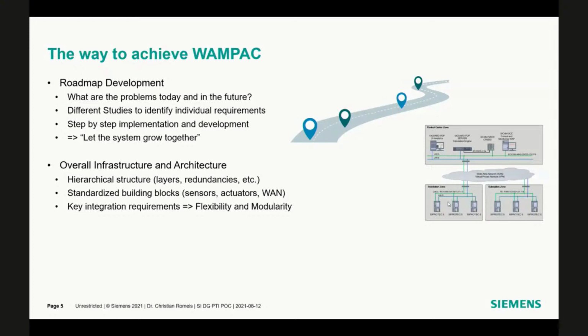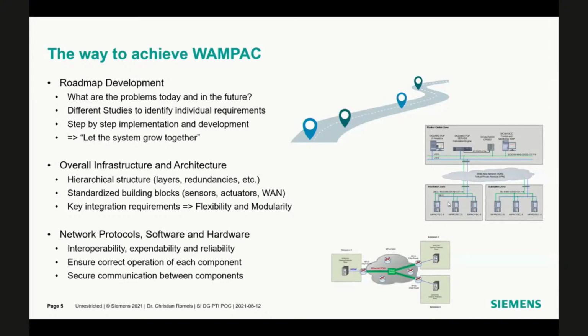And also you have to define standardized building blocks for you. Okay, which sensors I want to use, which actuators I want to use, what should I use in the wide area network, and you need to define key integration requirements. So it just must be flexible and expandable. And also you think about modularity, especially in the case of devices, because you can say, okay, I want my PMU standalone, or I can say I want my PMU in a protection device, for example, because I think most of the vendors have the possibility to have the PMU functionality in the protection device.